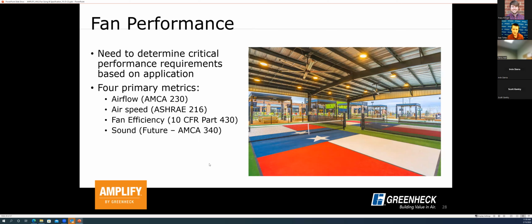Then from there, again, fan performance is really the next step in determining an appropriate selection. So we really need to understand what are the critical performance criteria and what are our requirements for the given building type and application that we've identified. So when it comes to HVLS fan performance, there's really 4 primary metrics, not too dissimilar from other fans and other equipment that you're specifying today. The 4 major performance criteria are airflow, air speed, fan efficiency, and sound.